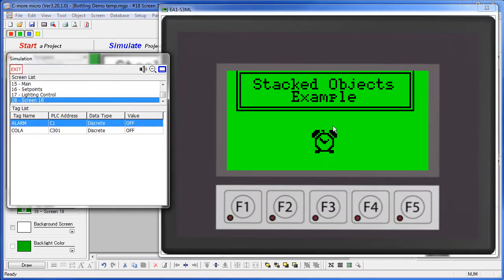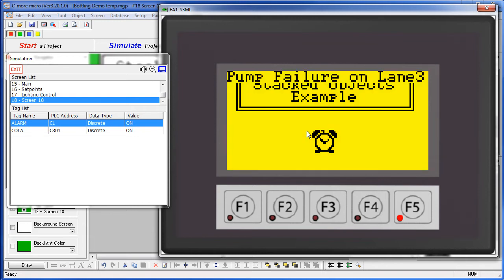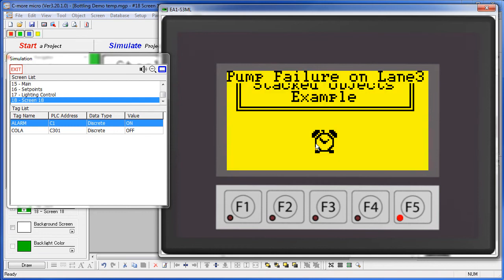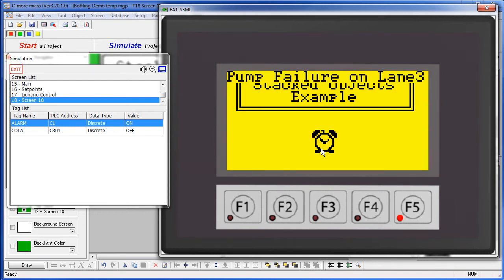So again, most of this area is covered by the cola tag. So when I click on this graphic, as you can see over here, only the cola tag is changing. If I move my cursor up to a region where the alarm button was exposed, then sure enough the alarm tag gets set, but the cola doesn't. So that's important to understand – the only objects that work are the ones that are visible under a graphic.